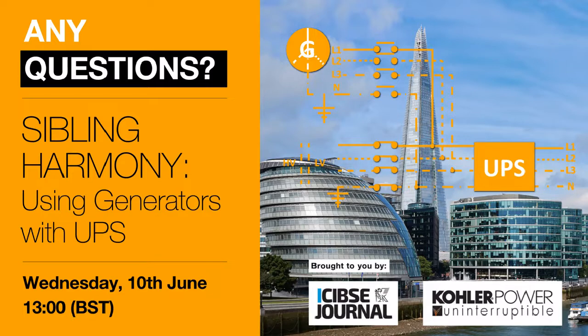You know, if we have a good 10-15 minute autonomy on the UPS, and we're starting the generator within 30 seconds, we've still got 9 to 14 minutes left of battery. So we can do many short mains failures. There is no need to keep the generator running until it's fully charged.